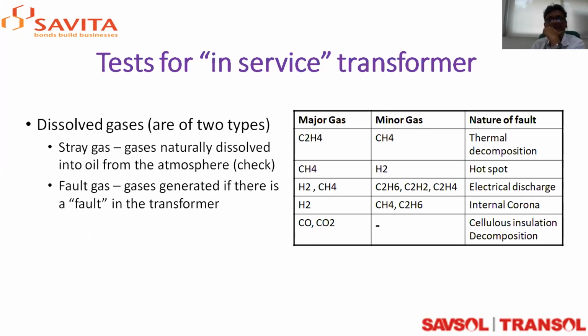As the sir said in earlier slides, dissolved gas analysis of an in-service transformer is one of the important tools. I am just briefly touching on this. When you consider dissolved gases, there are basically two kinds: one is the stray gases and the other is the fault gases. Stray gases are gases that naturally dissolve in the oil from the atmosphere. Fault gases are generated when there are hotspots. Everybody knows there is hotspot generation near the coil, and because of it there is a point of very high temperature. The molecules which come in contact with that high temperature sometimes degrade, and these gases are produced. So these are fault gases.